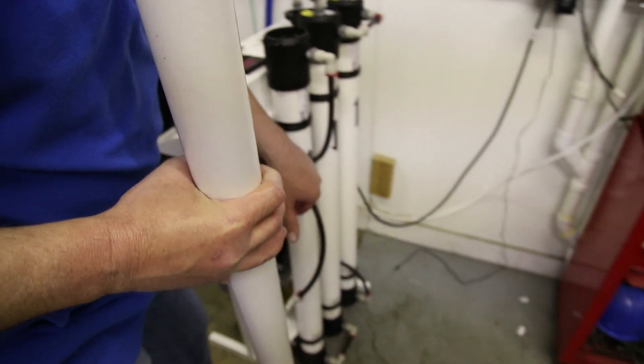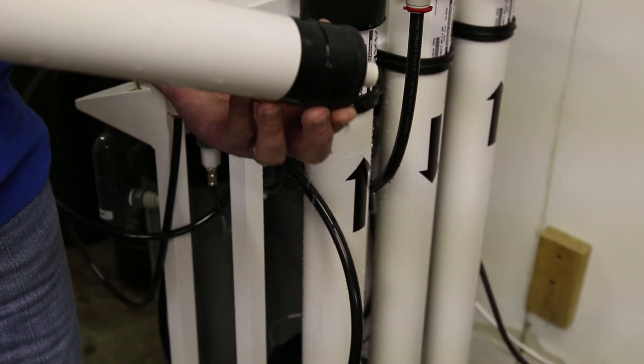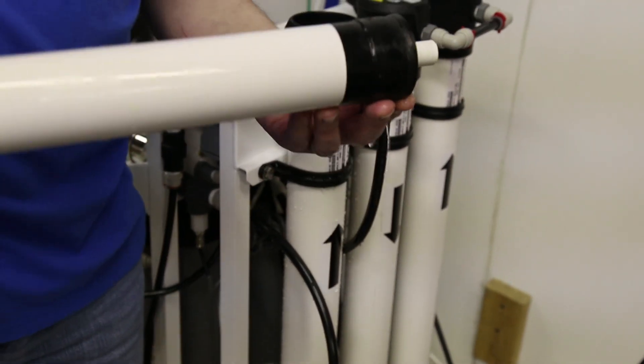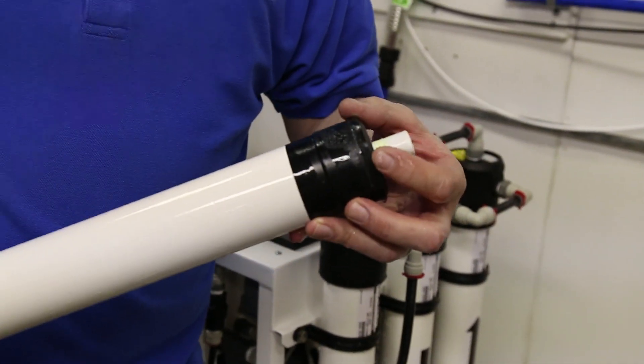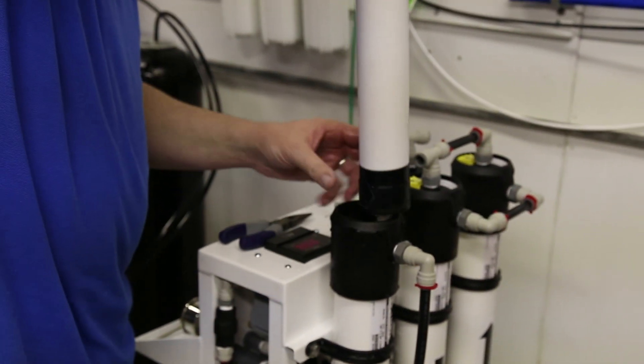Now I want you to see this skirt seal. As you can see it kind of flares out. What happens is when water comes in here, it pushes that seal out and seals this outer band and it forces water to push through the membrane. This is always going to be on the feed side of the membrane housing.